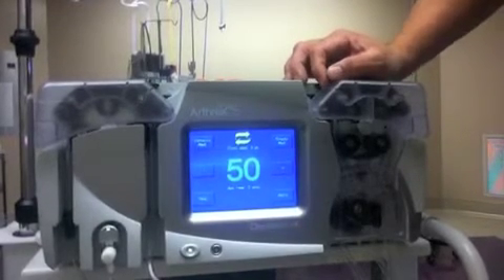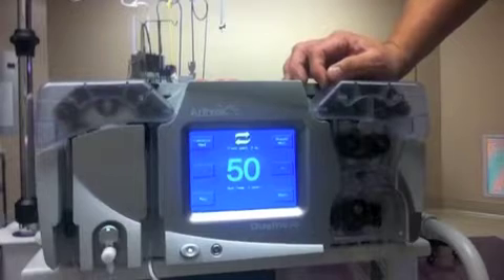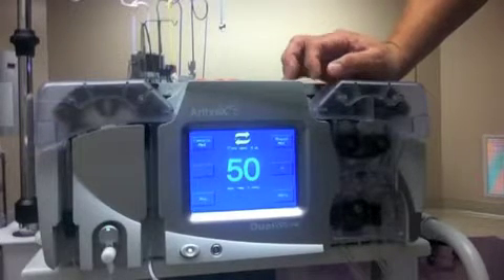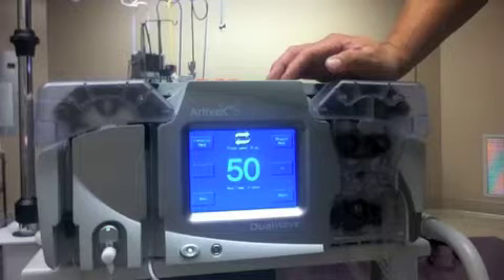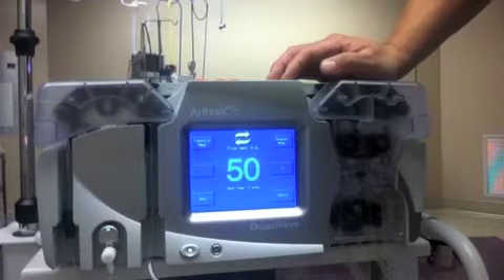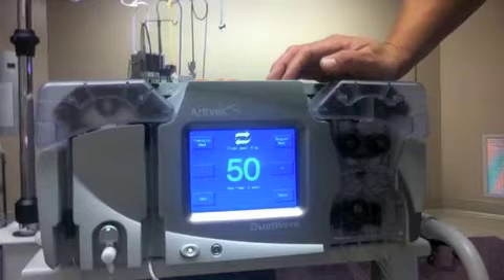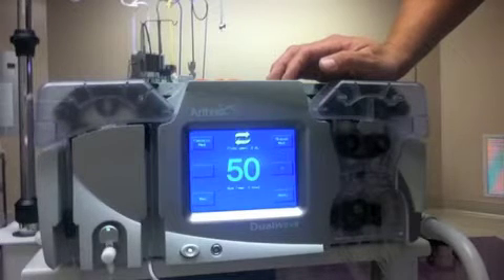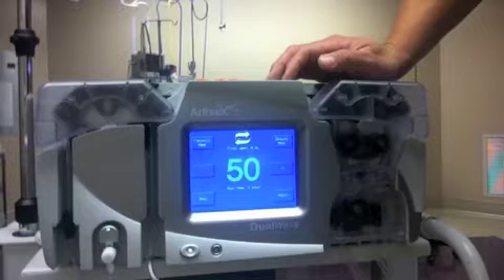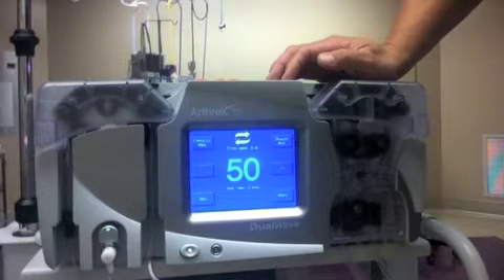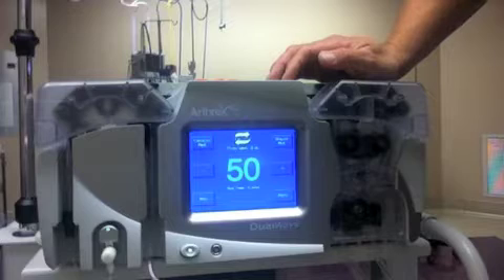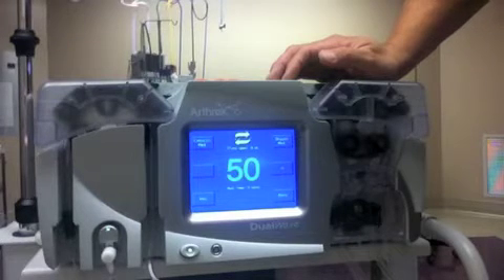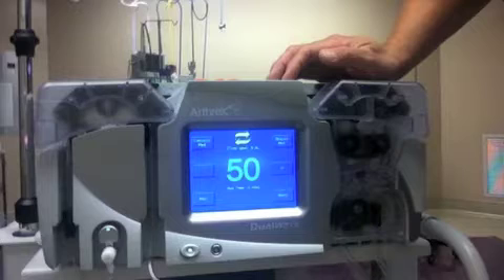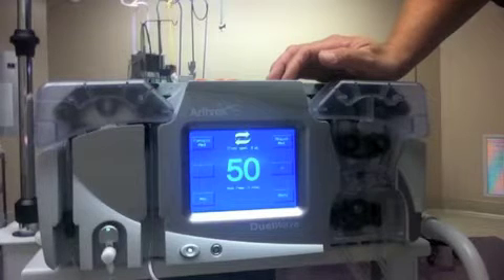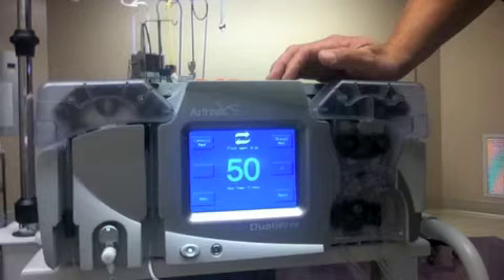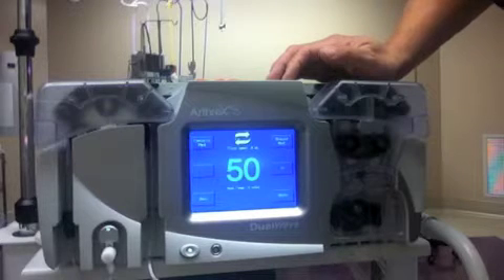Now again, it's critical that the baseline be established with the shaver handpiece along with the pump in order to allow for communication. Since this pump acknowledges when the shaver is turned on and therefore accounts for that extra suction and distension loss by way of boosting the pressure at the time that the shaver's on, it's really important for it to function properly that you get off to a good start. The reality, as I know and you know, of the situation is you don't always have a chance to first plug in the shaver and then the tubing. Typically everything's thrown on at once.